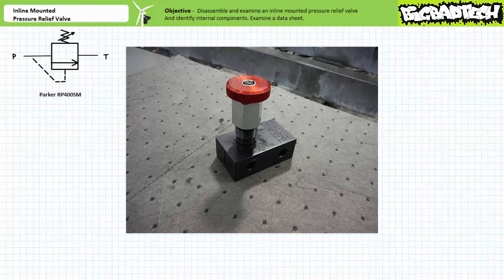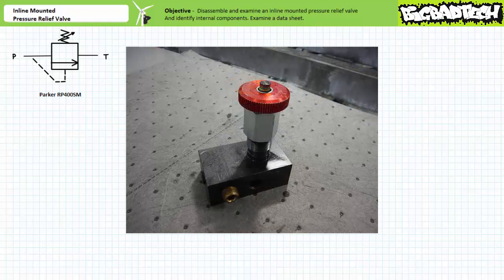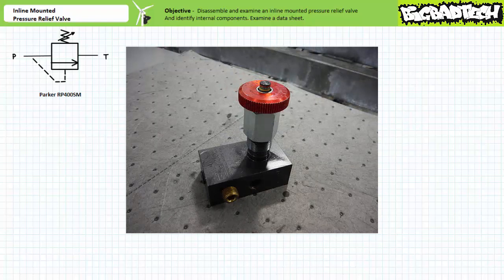First, the valve body has five ports. Two on one side, the pressure and vent connection. Two on the other, another pressure connection, purposely plugged, and the tank connection. Finally, a purposely plugged gauge port intended for a pressure gauge indicator. Flipping the valve over, you'll note each port is clearly identified on the body.